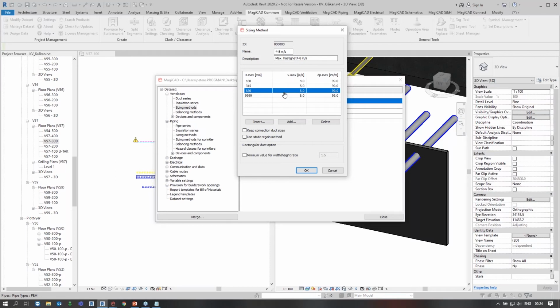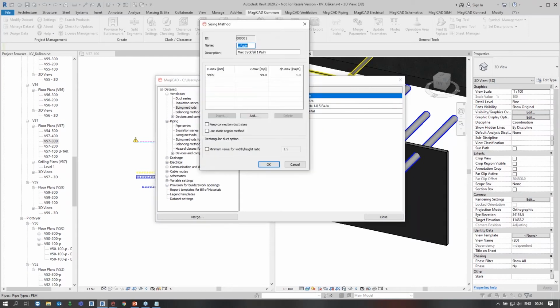And what's happening if I go for the 1 Pascal per meter, this one, if I'm running the sizing, and the pressure drop in my duct is above 1 Pascal per meter, then it's going to change the size of the duct, and then, okay, it needs to be this size, and then it checks, okay, is it under 1 Pascal per meter? Yes, it is. So it can check if I have drawn a too big duct. Maybe I have 0.5 Pascal per meter in the duct, then it's going to shrink it and make it smaller and optimize to get close to 1 Pascal per meter. It can go both up and downwards with this.